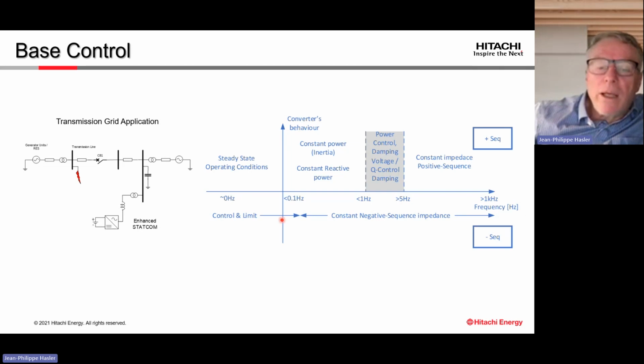It's only when we have to limit this negative sequence that we will have a current limiter, or we will change the operating point of the negative sequence control. But nothing will happen at very high or relatively high frequency. What I mean is above 1 Hertz or something like that.